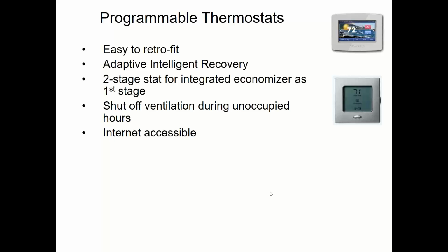So there's not really many thermostats that can do both of those things. With a building automation system you could decouple the ventilation schedule from the temperature schedule. But for most systems, those are one and the same. So you're probably going to let it go all the way to 5 p.m. Different, interesting question you had there. You can make the stats internet accessible. This in and of itself typically doesn't save any energy, but it's going to make things easier to be done. And one of the problems we had is that programmable stats are not easy. That's why people don't do it.